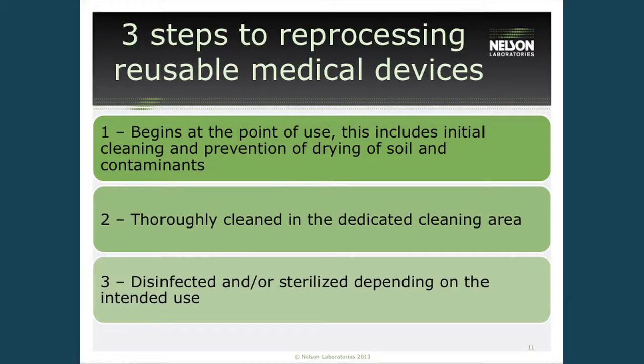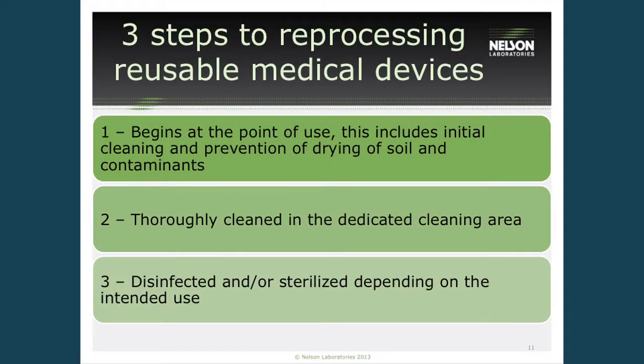So basically there are 3 steps to medical device reprocessing. And this begins at the point of use, which is usually in the surgical setting, and that includes a pre-cleaning at the bedside. And this can remove any of the debris and prevent the drying of any type of soil onto the devices. Next, the devices are moved into a central processing area where they are thoroughly cleaned in a dedicated cleaning area. And then after that, depending on what the device is and how it'll be utilized in the human, it'll be disinfected or sterilized for the intended use.